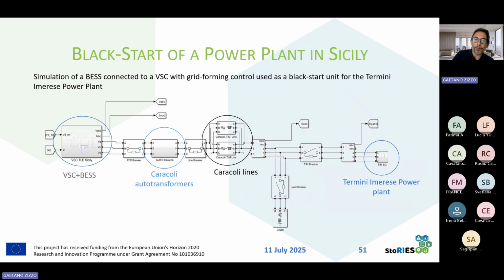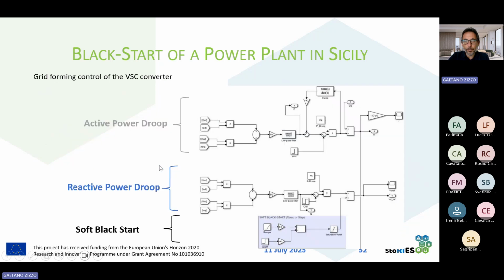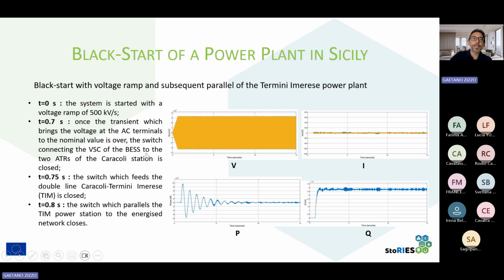Another case study: a black start of a power plant in Sicily. Here we have controlled the battery storage system with the grid forming control to energize the line that supplies the Termini Imerese power plant. Termini Imerese is an important power plant close to Palermo, and it will be the closest power plant to the new HVDC connection between Sicily and Sardinia, that is the West Tyrrhenian link. The system controlled with the grid forming control has been used for a soft black start. So the system is started with a voltage ramp of 500 kilovolts per second. After 0.7 seconds, the voltage has been established.